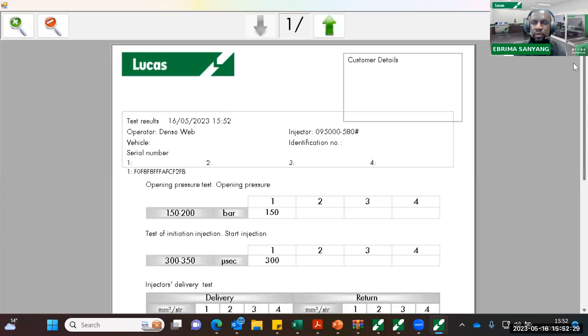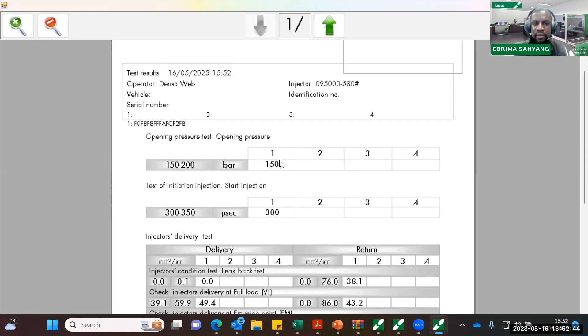Okay, so this is the information you need. This is the reference number of the injector, the customer or the name of the operator. There's the coding number in here, and what happened in the tests. What we're looking for is 150 to 200. So we have 150. And these are the deliveries and the returns, right? The deliveries are 39.1 to 59.9. So this injector has injected 49.4, meaning that this injector is good to go.